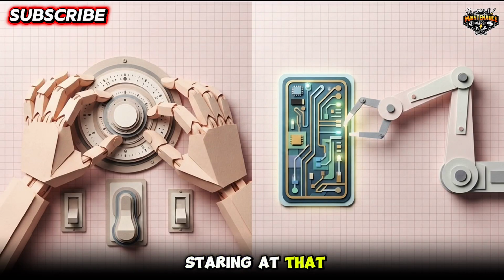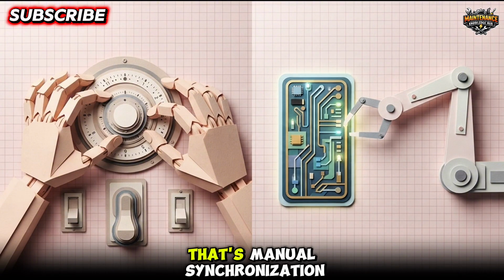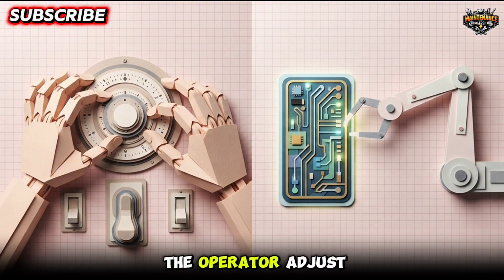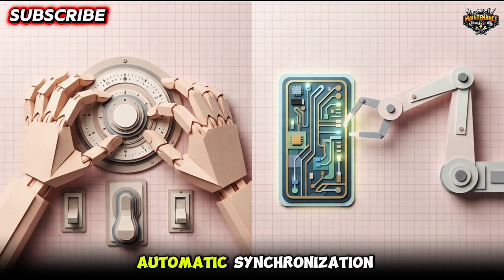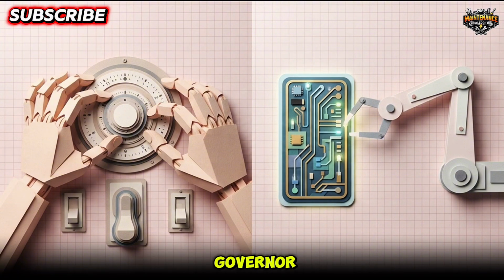Historically, staring at that synchronoscope and making the final call was entirely up to a human operator. That's manual synchronization. The operator adjusts the voltage, tweaks the frequency, watches the dial like a hawk, and hits the button. But today, modern power plants almost entirely rely on automatic synchronization. You've got an automatic synchronizer that continuously monitors all the conditions, talks to the AVR and the governor, and fires off the close command itself with absolute machine-level precision.